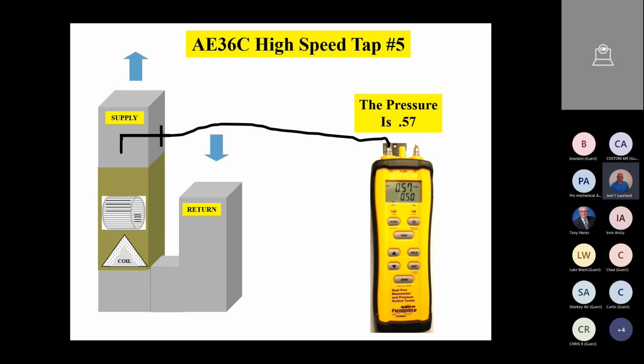Now, I find that most of the time you're going to have issues on return. You just don't have enough return air on the job site. But sometimes you'll have undersized ductwork, or you'll have issues on the supply side as well. And so in this example, maybe the company ahead of you, or maybe the system's 10 years old, and a lot of different companies have worked on it. The technician goes out and puts it on high speed tap, and he's blowing whatever air he can blow. He doesn't really understand what's going on. Then you guys come in with your tools and start taking measurements. Say, golly, no wonder they're having issues. We're not moving enough air. So it's important that we understand what we're looking at when we look at static pressure.